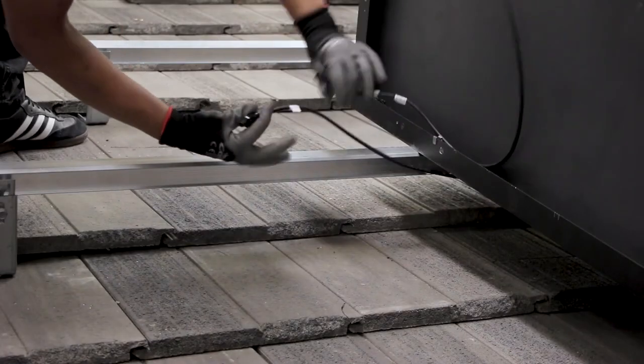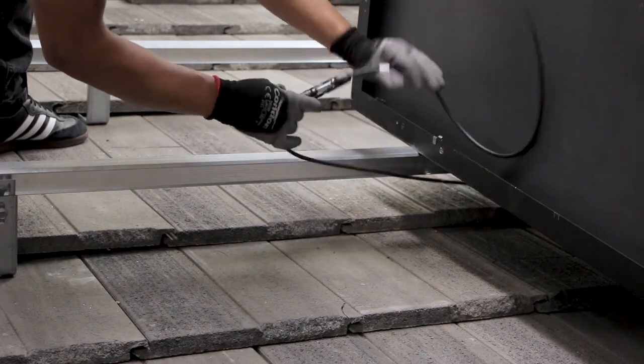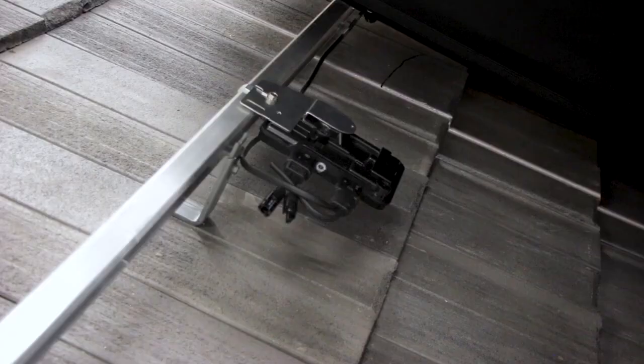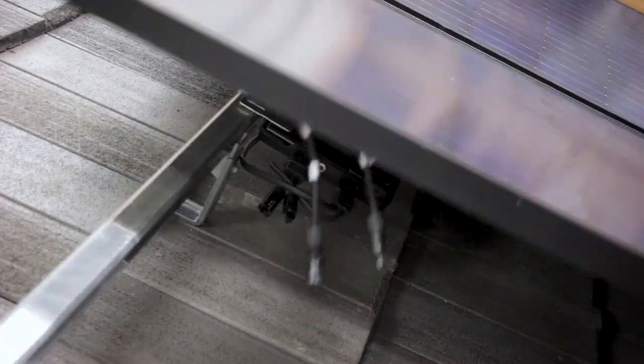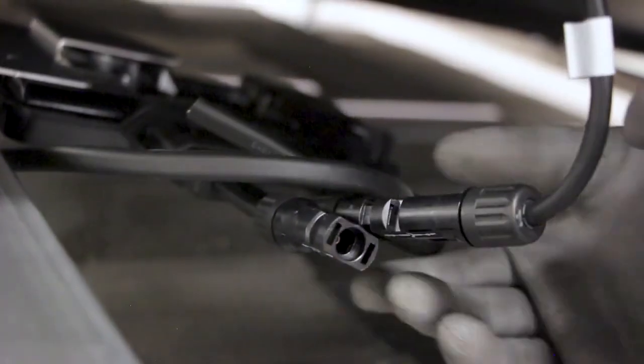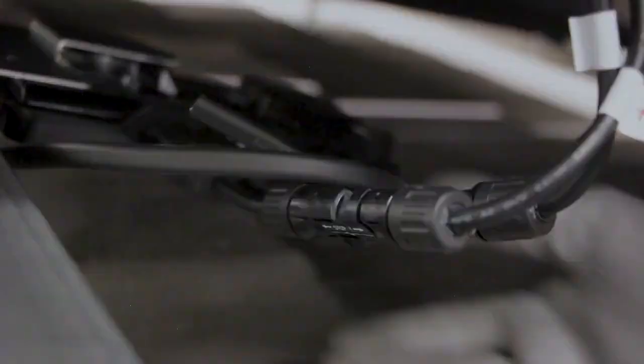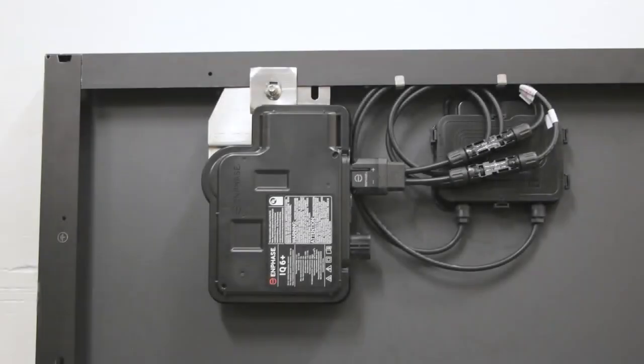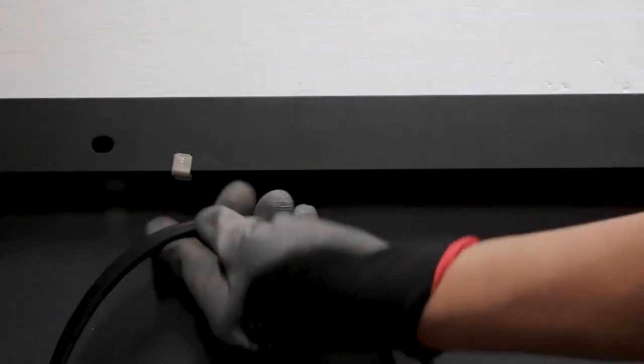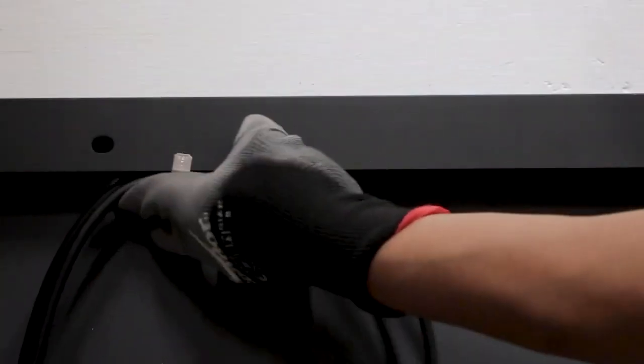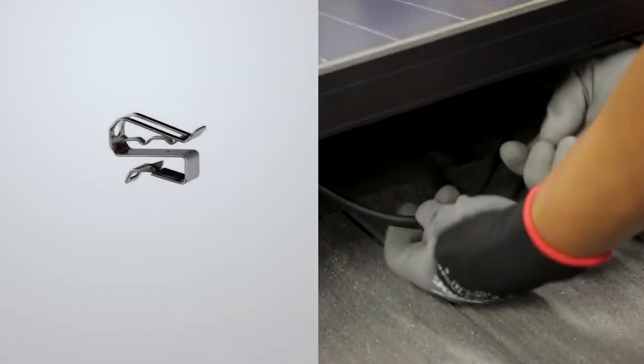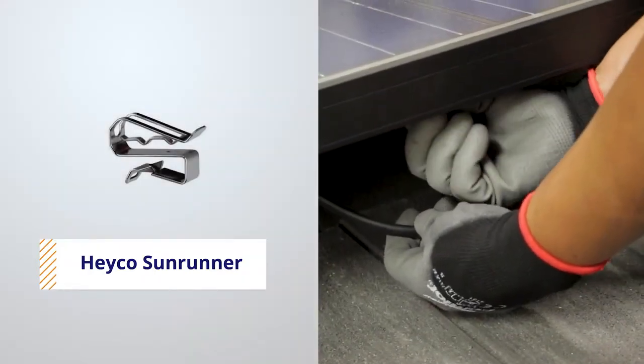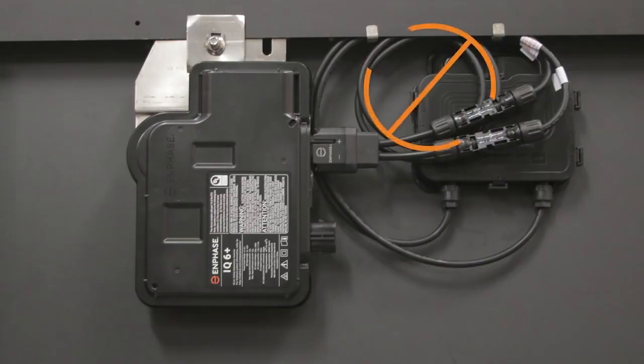As you lay down each module, make sure to connect the module PV wires to the adjacent module in the row or to any microinverters or optimizers that may have been installed to either the rail or module frame. MLPEs that have been attached to the module frame can be wire managed before bringing them up onto the rail. Keep wires from sagging by clipping them to the module frame using generic wire clips. We recommend the Heyco Sunrunner clips for clipping wires directly to the module frame. NEC requirements also stipulate a minimum bend radius, so tight coiling or bending is not advisable.